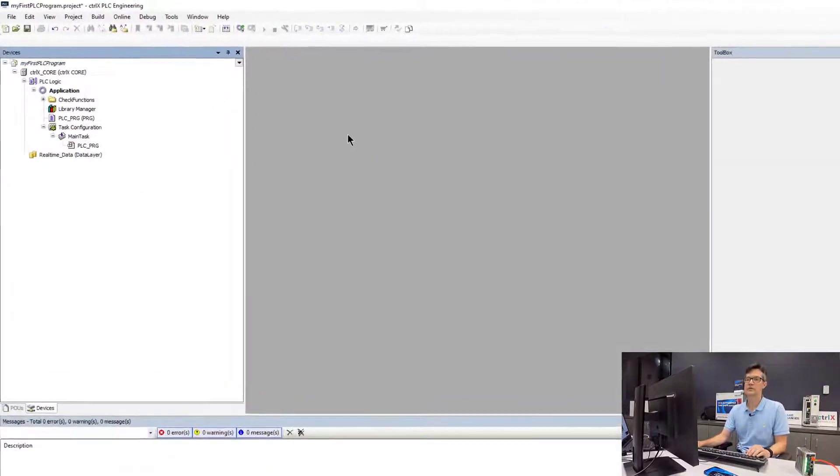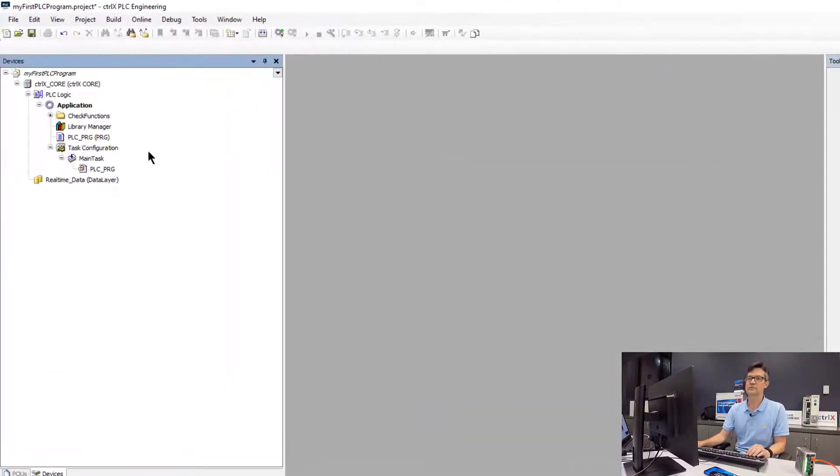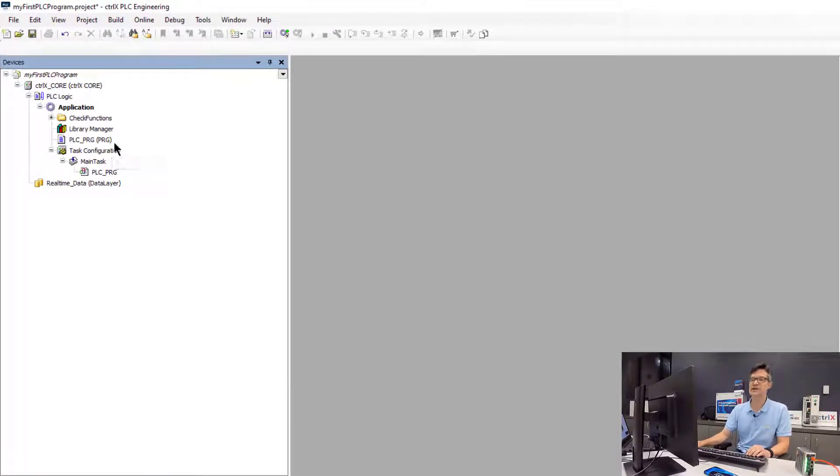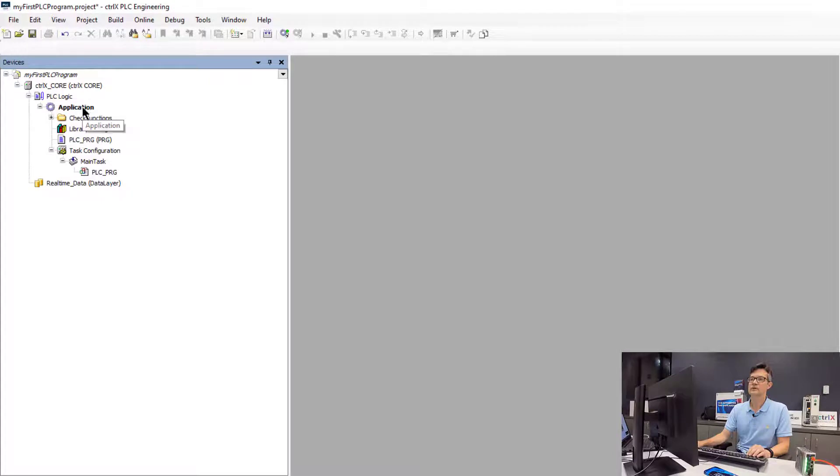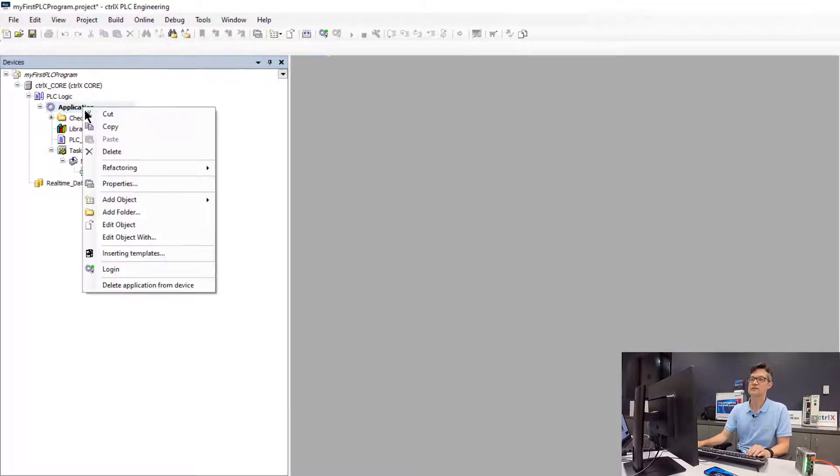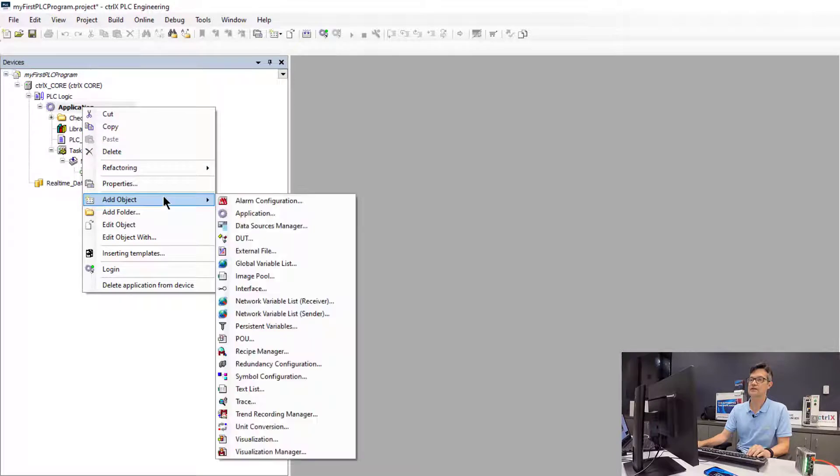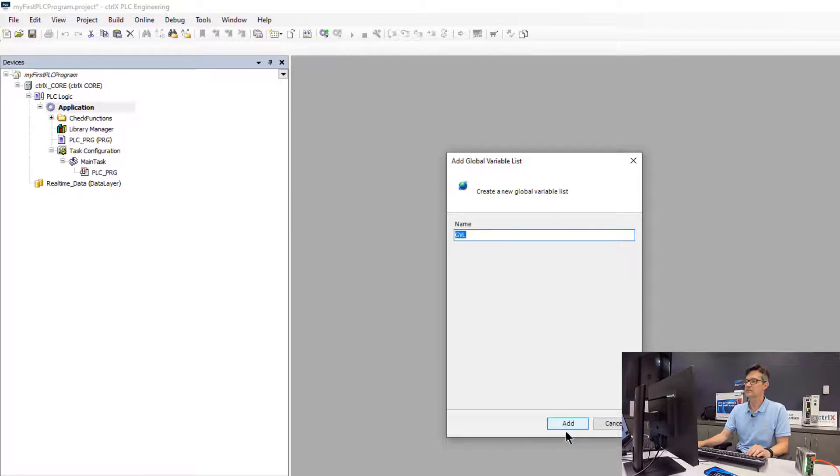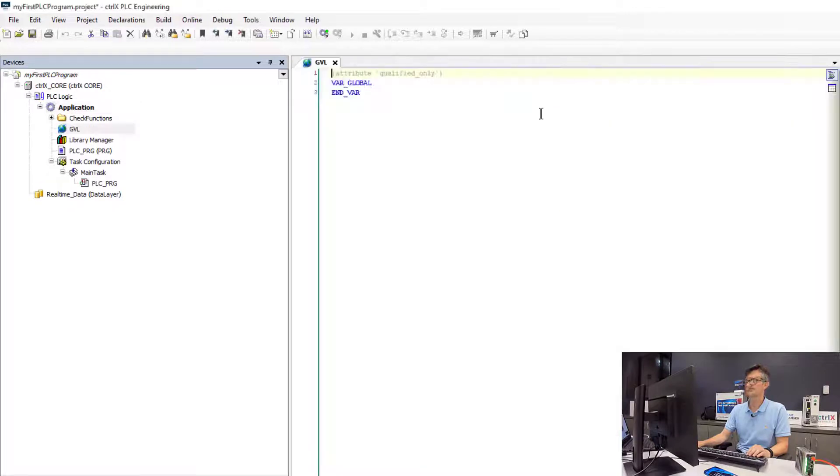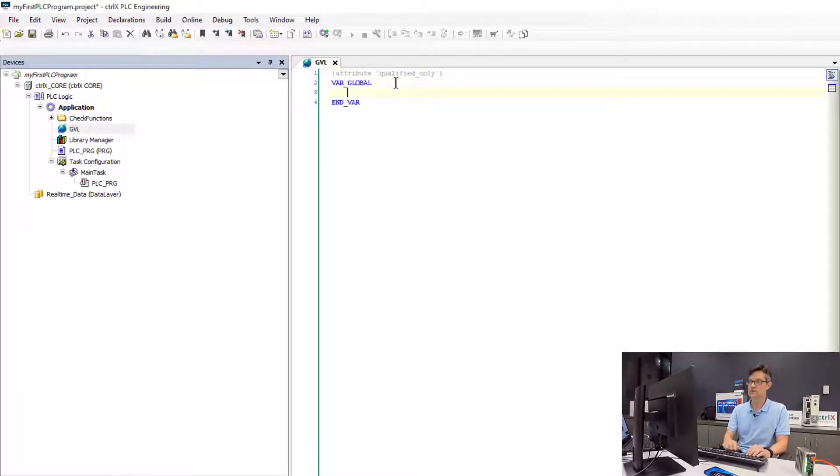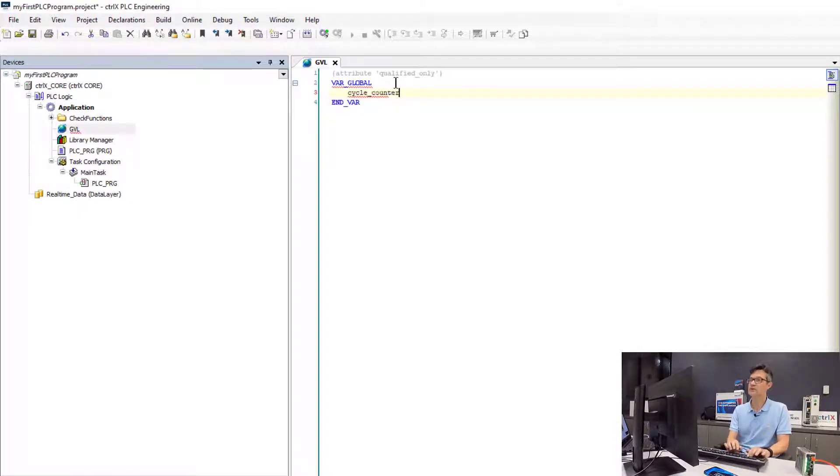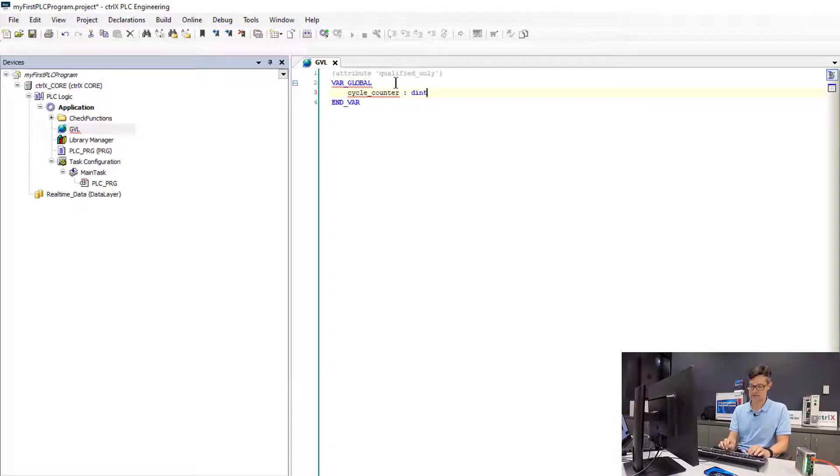The first thing we are going to do is make a simple application that just increments a counter on a variable. So the first thing that we will need to do is add a global variable object to our project, and we will leave this with the default name GVL. So inside here we will now go ahead and declare a variable. We will call this variable cycle counter. It will be of type DINT.